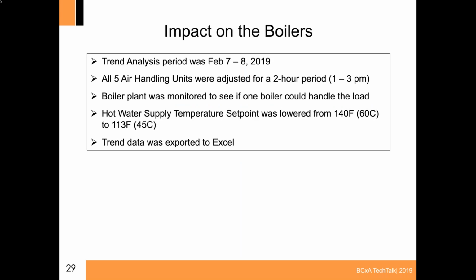So what was the impact on the boilers for the hot water heating system? We chose an analysis period in February when the outdoor conditions were predicted to be roughly the same from Environment Canada. All 5 of the air handling units in the school were adjusted to what we knew were roughly the return air damper settings for a 2-hour period from about 1 to 3 p.m. in the afternoon. And the boiler plant was monitored to see if one boiler could handle the entire load of the school. The hot water supply set point, because the cores were then roughly balanced, we were able to lower it from 140 Fahrenheit or 60 Celsius down to 113 Fahrenheit, 45 Celsius. And that trend data was then exported to Excel for analysis.